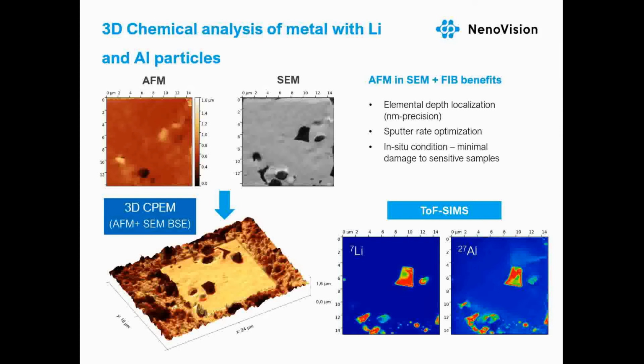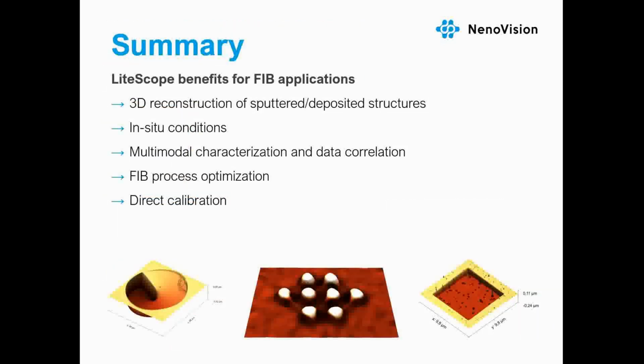The LiteScope incorporates innovations in design of atomic force microscopy, enabling its integration with SEM and focused ion beam systems into a single powerful analytical tool. The key prerequisite for full compatibility of LiteScope with focused ion beam applications is its ability to tilt into a typical FIB milling configuration where the sample surface is normal to the incident ion beam. The biggest advantage of combining AFM with focused ion beam is the direct monitoring of nanofabrication process in in-situ conditions and three-dimensional reconstruction of the modified structures.